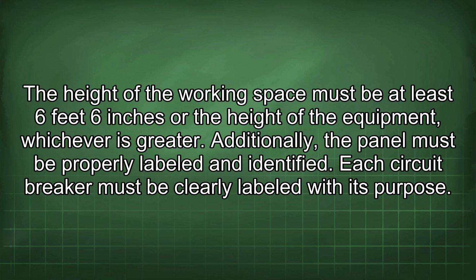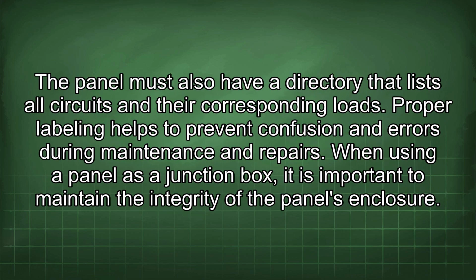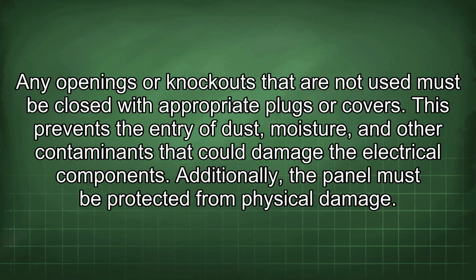Additionally, the panel must be properly labeled and identified. Each circuit breaker must be clearly labeled with its purpose. The panel must also have a directory that lists all circuits and their corresponding loads. Proper labeling helps to prevent confusion and errors during maintenance and repairs. When using a panel as a junction box, it is important to maintain the integrity of the panel's enclosure. Any openings or knockouts that are not used must be closed with appropriate plugs or covers. This prevents the entry of dust, moisture, and other contaminants that could damage the electrical components.